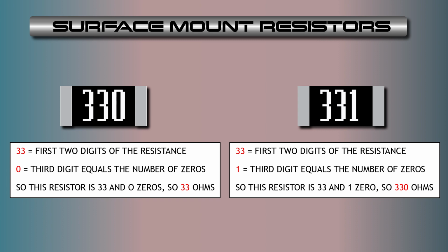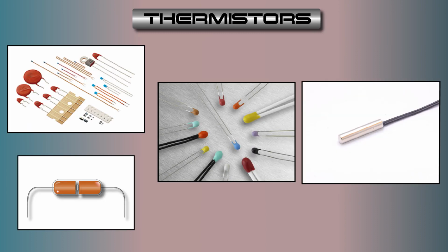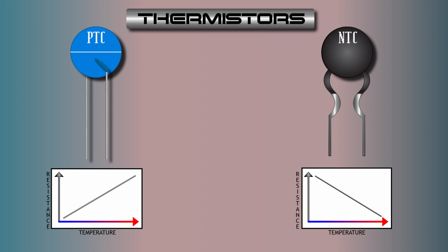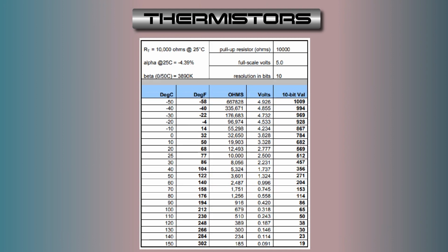The special type of resistor we're concerned with is the thermistor. The thermistor is a temperature-sensitive resistor, which the resistance value changes with the change in temperature. There are two main types of thermistors: the negative temperature coefficient, or NTC, and the positive temperature coefficient, PTC. The NTC means that when the temperature goes down, the resistance increases, and inversely, when the temperature goes up, the resistance decreases. Thermistors have a different range, with the most popular being 10K ohm, or 10,000 ohms, which means 10,000 ohms equals 77 degrees Fahrenheit, or 25 degrees Celsius.